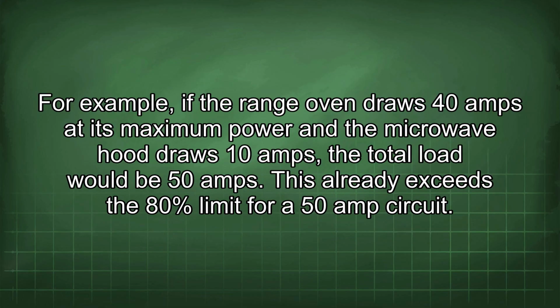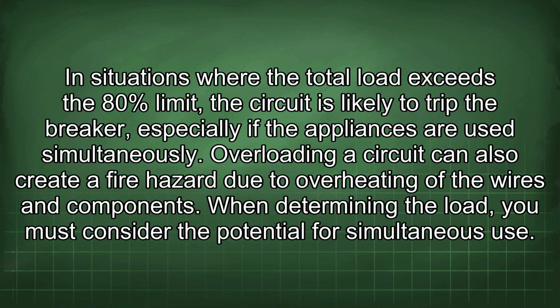For example, if the range oven draws 40 amps at its maximum power and the microwave hood draws 10 amps, the total load would be 50 amps. This already exceeds the 80% limit for a 50 amp circuit. In situations where the total load exceeds the 80% limit, the circuit is likely to trip the breaker, especially if the appliances are used simultaneously. Overloading a circuit can also create a fire hazard due to overheating of the wires and components.